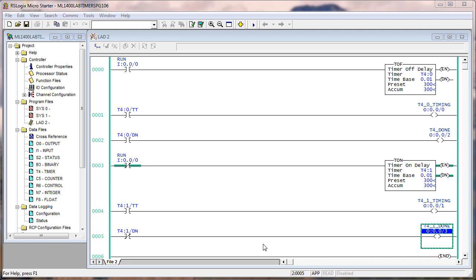The TON, rung three, when that bit is off, the rung is true. So when the rung is true, then we start the TON and the bits, the control bits, operate according to what you would expect. The enable and timer timing go on and when the accumulate equals the preset, it's done. The enable stays on and the done stays on but the TT goes off. The timer timing goes off.